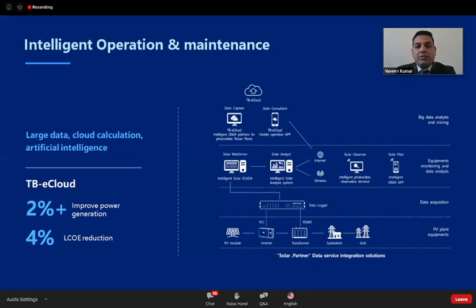Moving ahead to the second layer, where we have data acquisition, the data logger. TBEA also provides the T logger, which is known as the TBEA data logger, where we can interface all your PV plant equipment to a single data logger, whether it is inverter, transformer, MV switchgear, or weather monitoring system. So all can be interfaced with a single data logger of TBEA. After data acquisition, we collect the data at the T logger, then move to an upper layer, equipment monitoring and data analysis. TBEA has its own solar SCADA platform, known as Solar Watchman, where we can monitor the complete plant equipment in a single window.